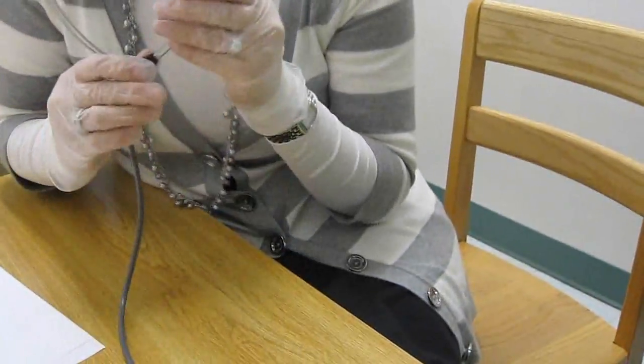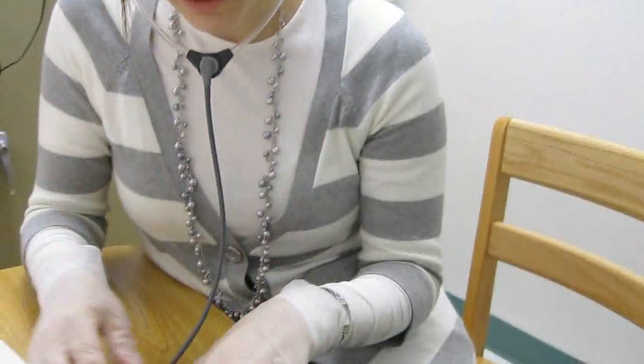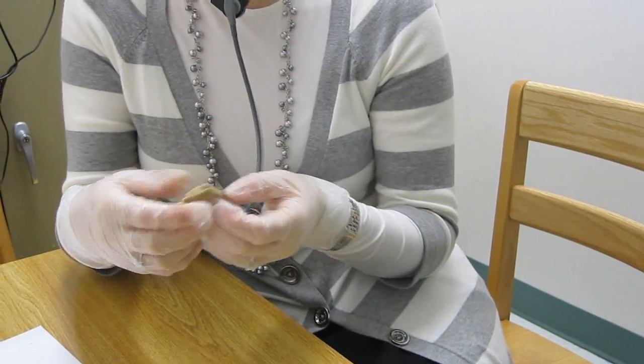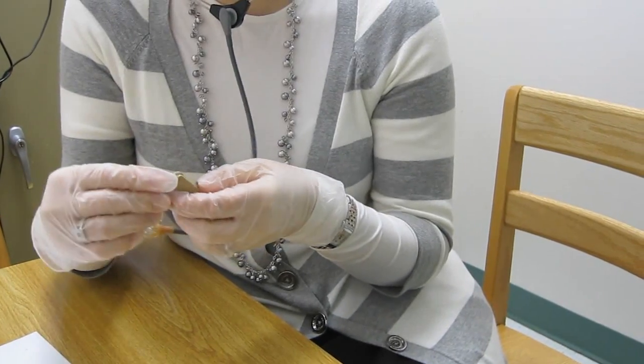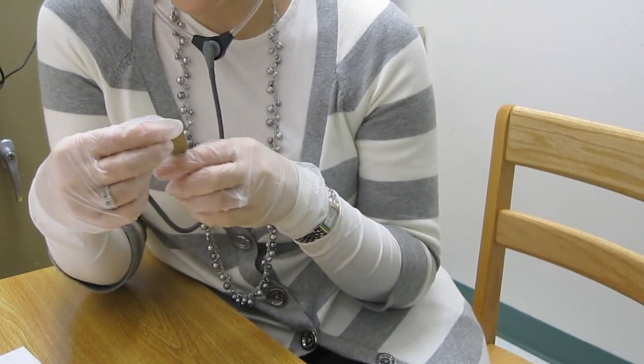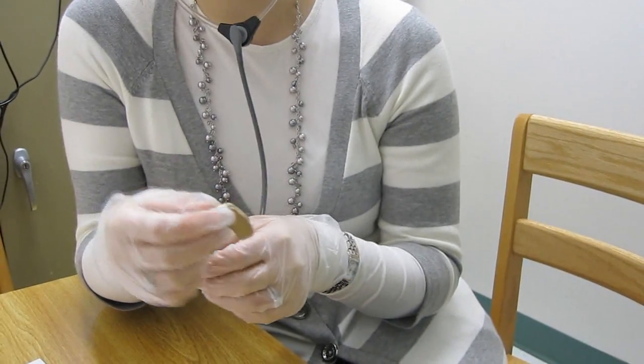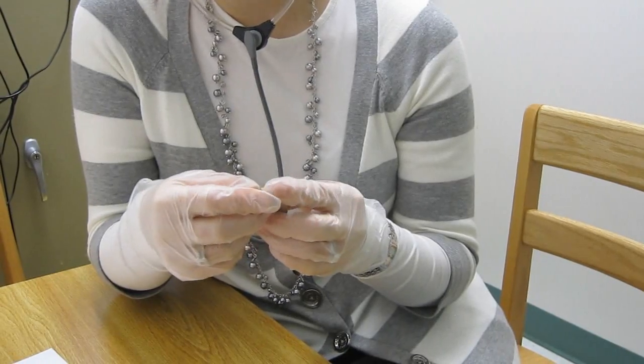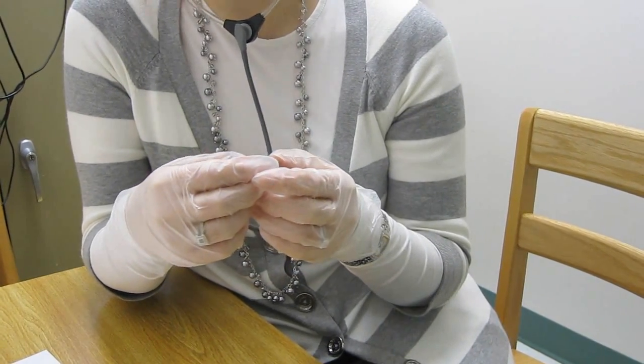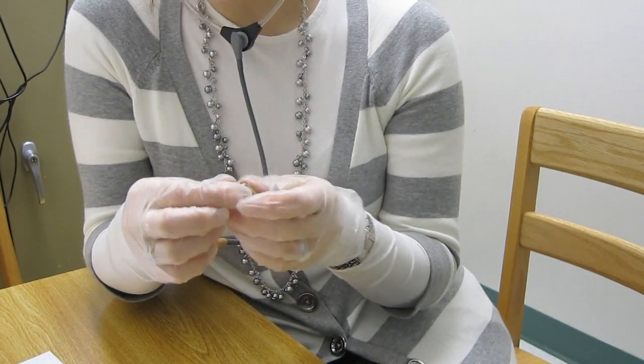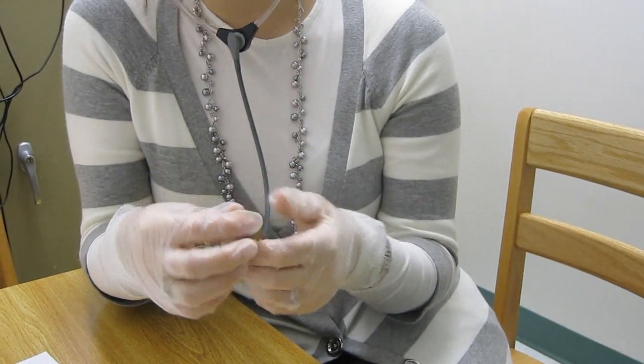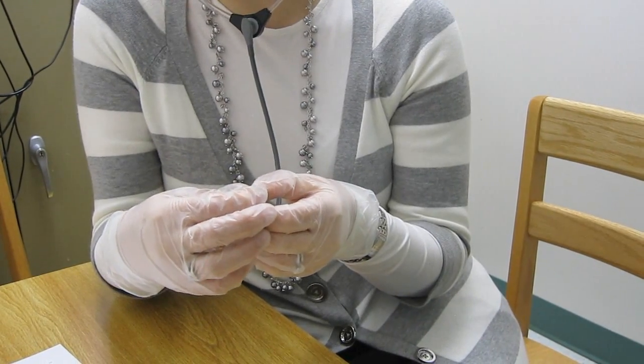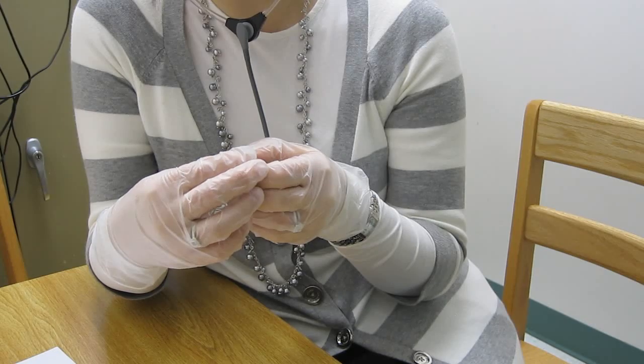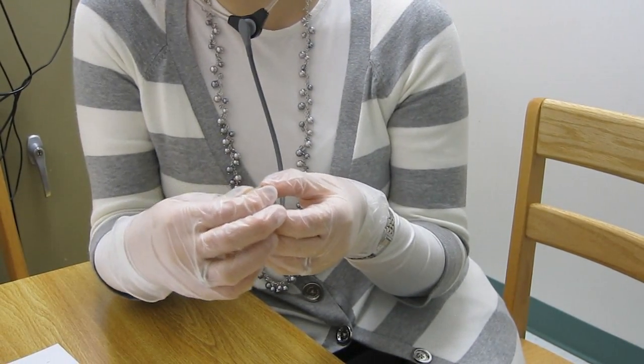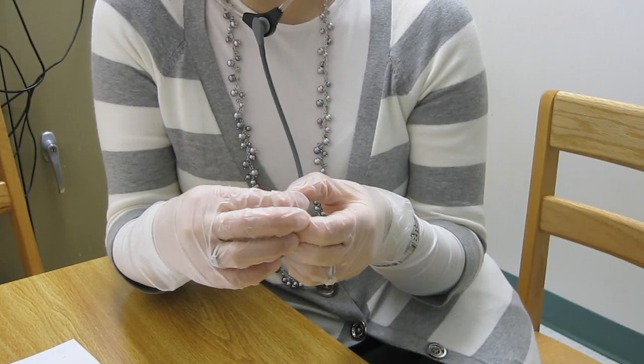Now we're going to do a listening check to make sure that this hearing aid is working properly. So you make sure that the volume is turned up and first that the hearing aid is turned on, which it is, and then you say the Ling sounds. Ooh, ah, ee, sh, and it is working. The signal is clear, there's no distortion, there's no static, there's no hum. The signal is not cut out. It doesn't cut in and out. Not when you press on the case, not if you move the hearing aid around. It's good, you hear well. The volume control is good. The signal does gradually get louder and lower as you move the volume control wheel, which does move easily. There are no breaks in sound or intermittency as the volume is changed.